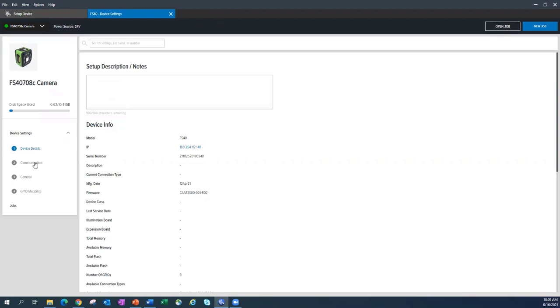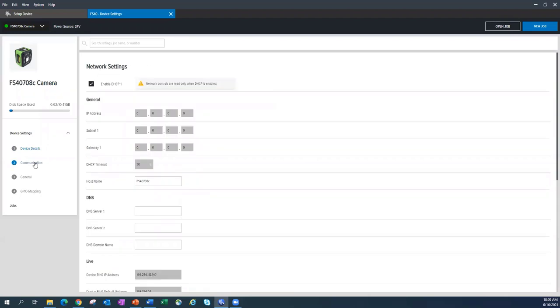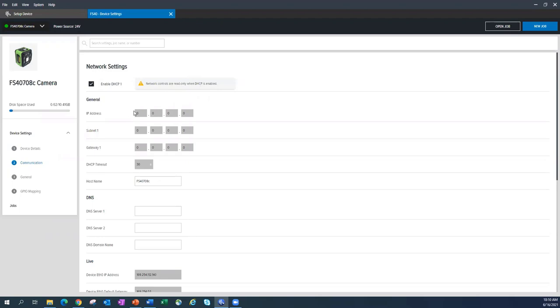Next, we'll dig down into some more commonly used tabs. The first one is going to be your network settings. You can see here this device is currently enabled with DHCP. When I am enabled in DHCP, you can see we gray out the ability to set an IP address and we also put a nice little message in here that tells you why things are grayed out. So when the network controls are read-only, I can't go ahead and make any kind of adjustments to my IP address. If I want to make a static IP address, I simply uncheck the DHCP, then type in the IP address, subnet, and gateway. All three of those are important to making sure this works. So you could type that information in here.